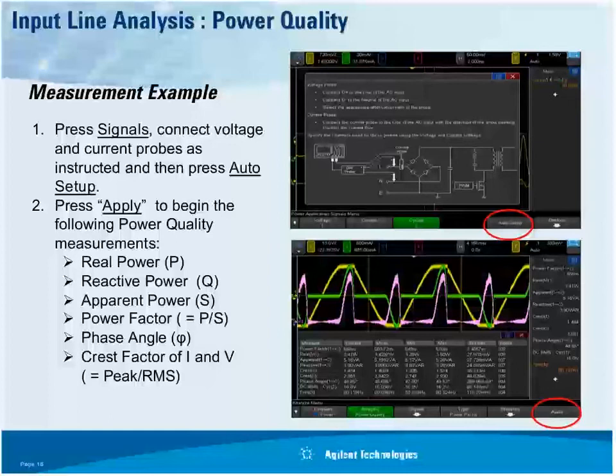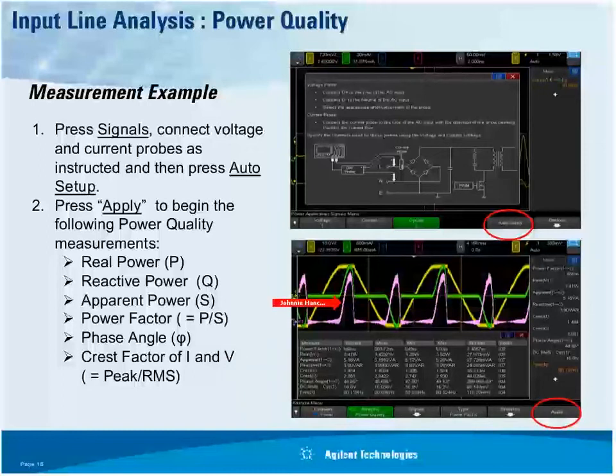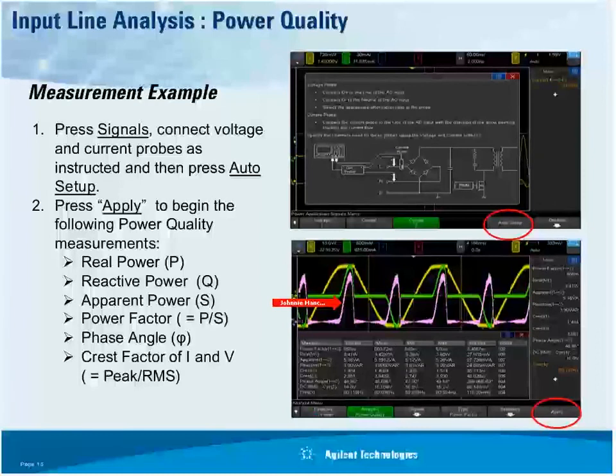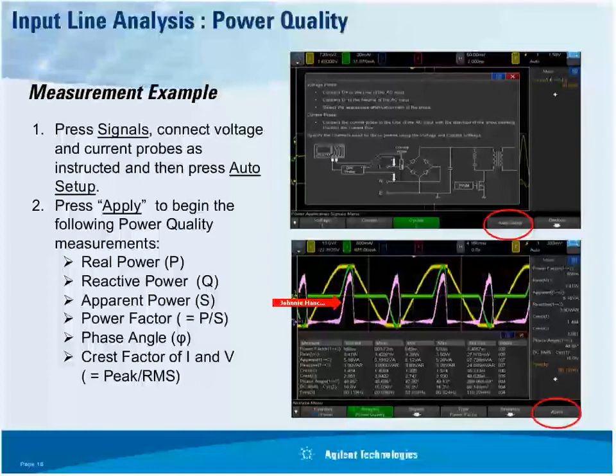Here you can see the results on screen along with statistics so you can see any variations. If you don't have the power measurement option, you can perform these measurements manually. Real power is not too bad — multiply channel 1 times channel 2 to get the power waveform, then take the average over N cycles. Apparent power: measure volts RMS and current RMS over N cycles, then multiply. Reactive power is more difficult but achievable.